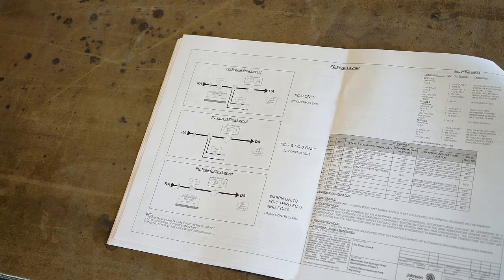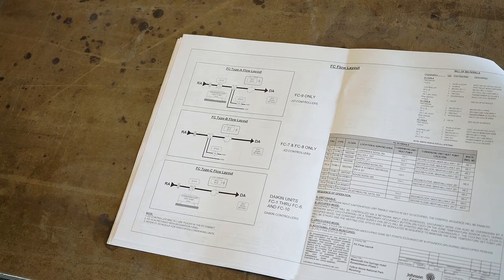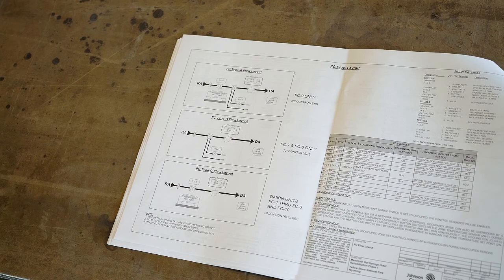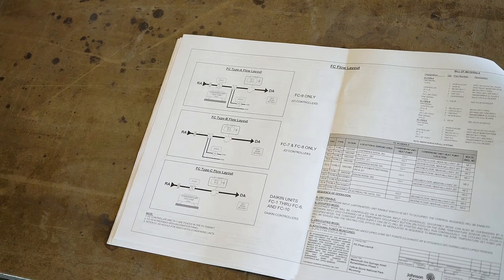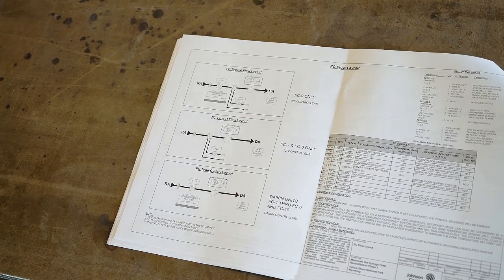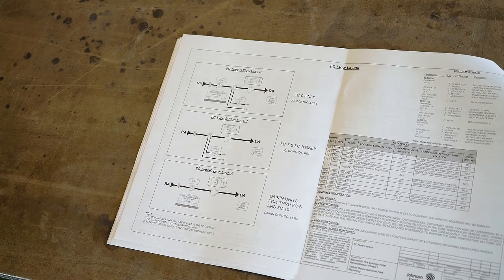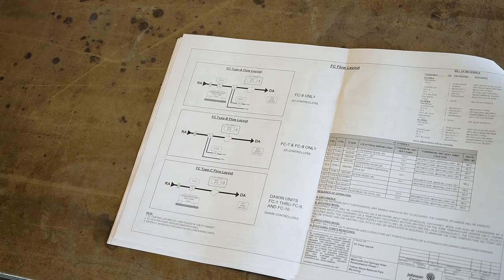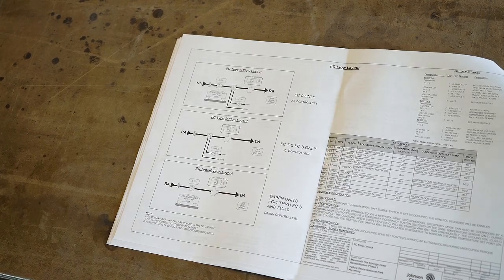So if you were talking earlier about what if that room's satisfied and this room's hot. If it's in cooling mode, which it probably will be most of the time, these rooms will try to maintain their individual cooling set points. So if this room needs cooling, it'll turn the fan on and turn the condenser on outside and cool this room, and if the next one's satisfied, it won't do anything. So you do have individual control that way on the different rooms up here. But not for heating if that one's in the cooling mode. I don't know if you're done with that job, right? No, I got it. Right.